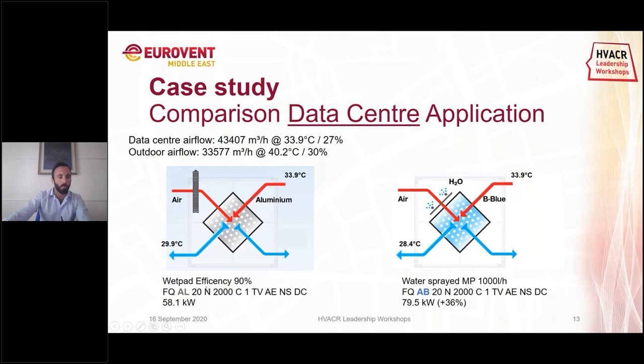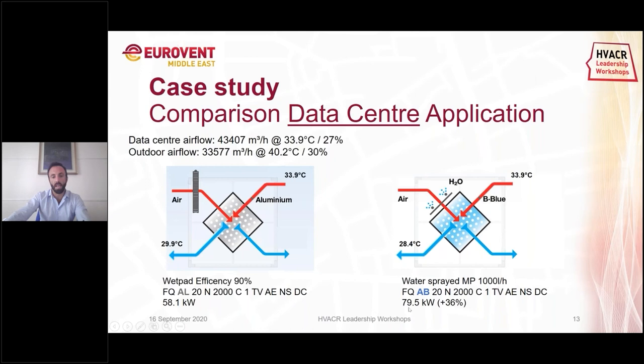With the wet pad at 90% efficiency, we get 58.1 kW of cooling capacity — going from 34°C down to approximately 30°C, about 4 degrees less. If we substitute the wet pad with the spray system and also wet the heat exchanger, we get 79.5 kW — that is a 36% improvement. This is because we are spraying water inside the heat exchanger. We are also not considering the pressure drop here, because the wet pad has a pressure drop throughout the year, whereas the spray system adds no extra pressure drop beyond the plate heat exchanger itself.